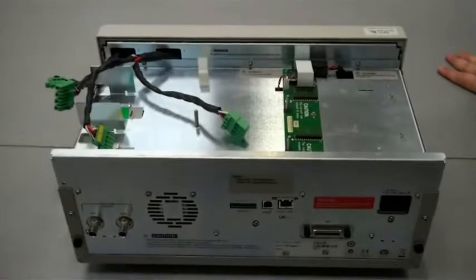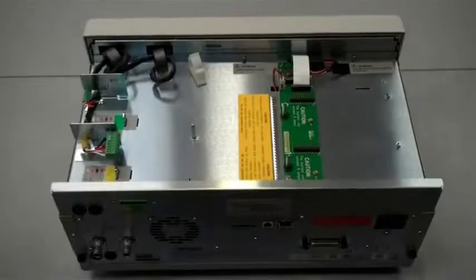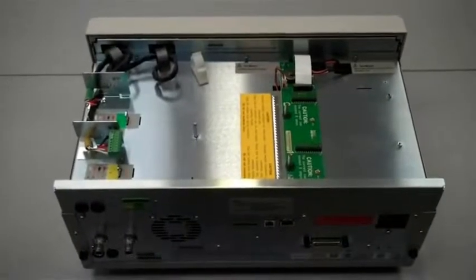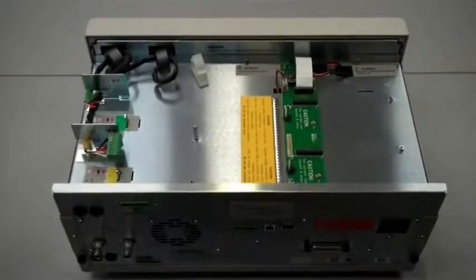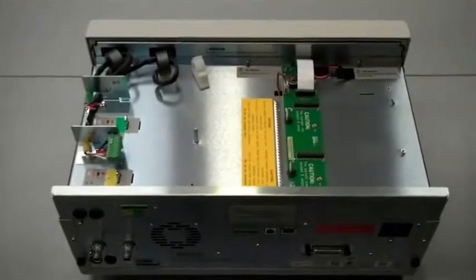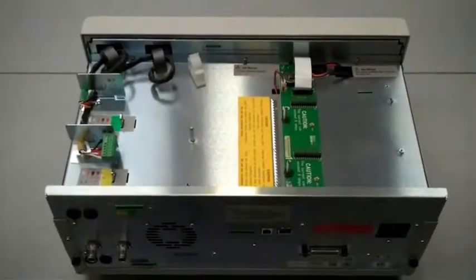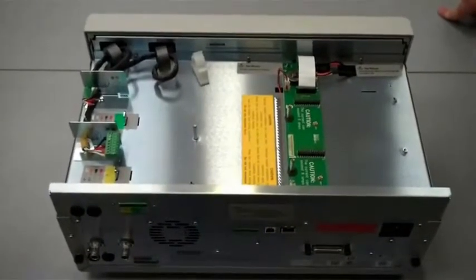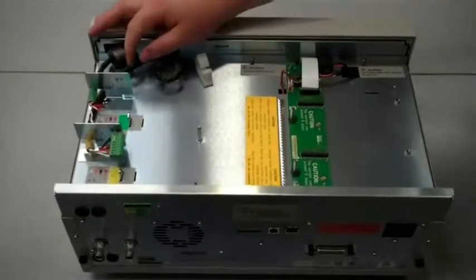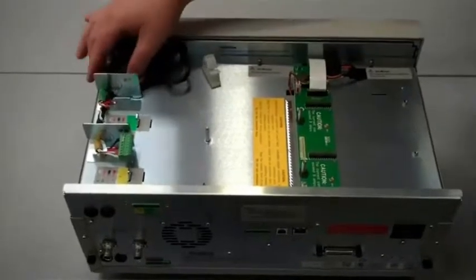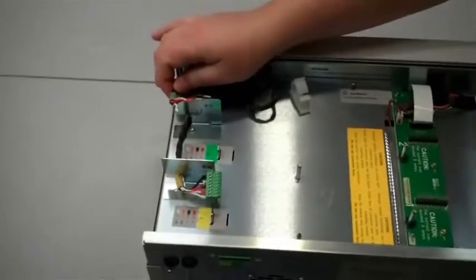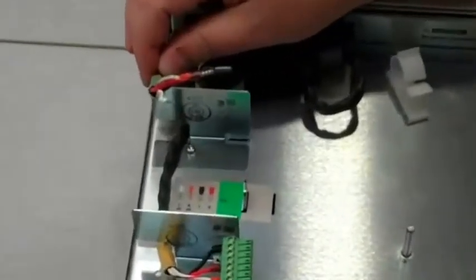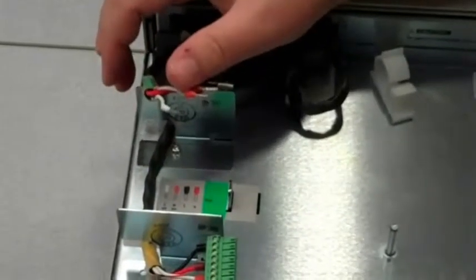Now let's take a similar look at the same area on the B mainframe. Here's the top of the B mainframe where you connect the module. You can see it's pretty different from the A. The first thing we're going to point out is this RFI strip here that connects the modules to the chassis a bit better. The other thing that changed quite drastically is the way we connect off the modules. Now instead of having the crimped on connectors and the split wire with the two connectors on it, we have one wire that you put the connector on yourself. You need to take the connector that came with the module when you purchased it and install it onto the wires here.